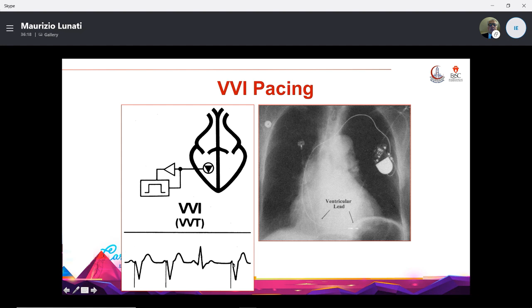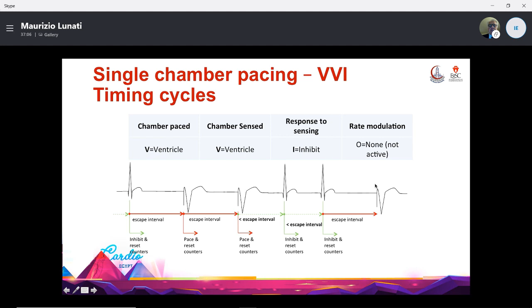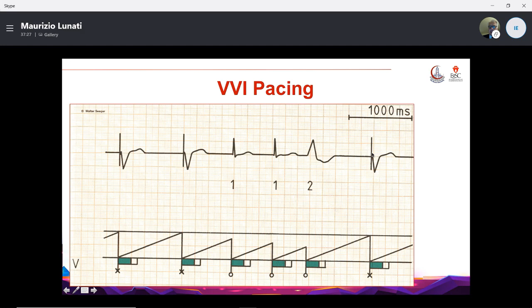These are the timing cycles of single chamber pacing. We are talking of ventricular pacing. I want to remind you that the first letter, V, means the chamber paced, the second letter is the chamber sensed, the third letter is the response to sensing. So we have a spontaneous intrinsic beat, escape interval, ventricular pacing beat, escape interval, ventricular escape beat. Now we have 2 spontaneous beats, and after the designed escape interval, there will again be a ventricular beat. And this is once more an example of the correct working of VVI pacing. Pacing, pacing, inhibition, inhibition, ventricular ectopic beat, and again ventricular pacing.